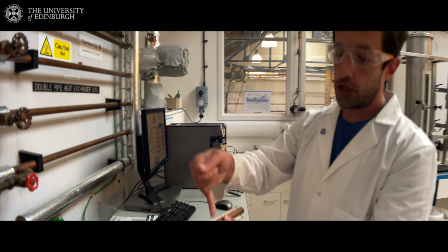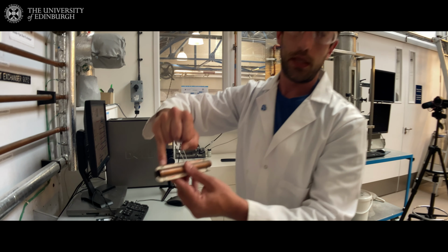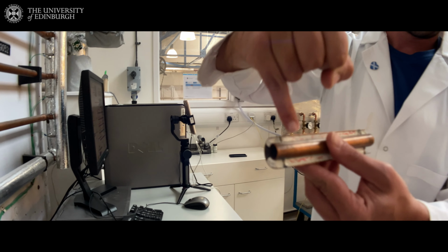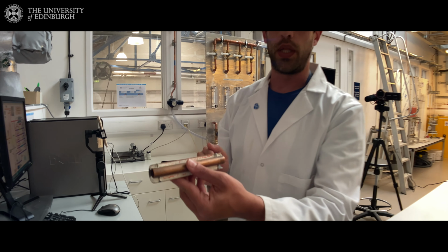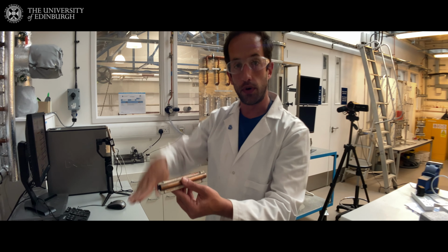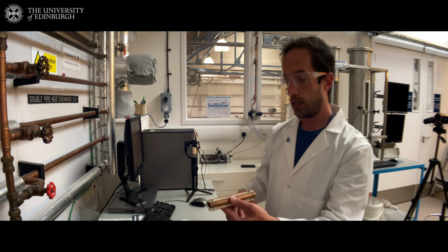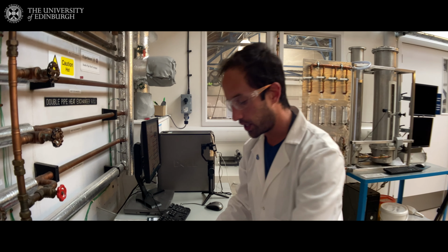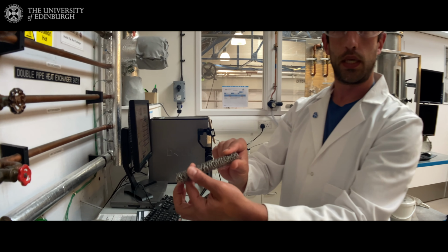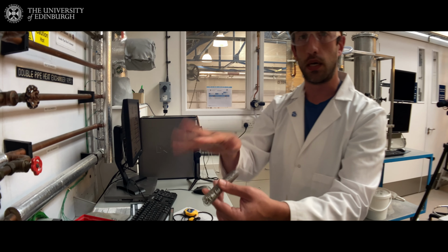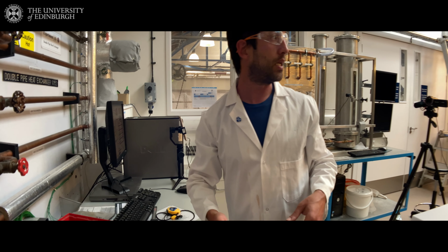Another important variation that we have in the outer shell of this heat exchanger 3 is these baffles that you can see here, these kind of cross sections. What this does is make the fluid in the outer shell divert and move and create a little bit of mixing and turbulence that typically gives more heat transfer. And there is also another of the tubes where there is a mesh inside. Again, this creates turbulence and provides greater heat transfer.